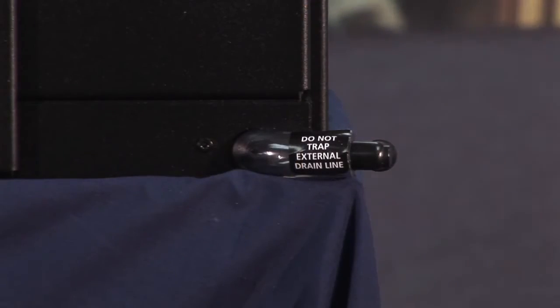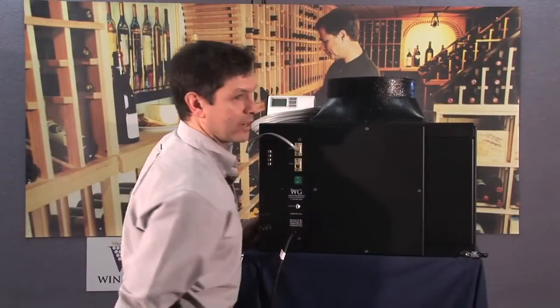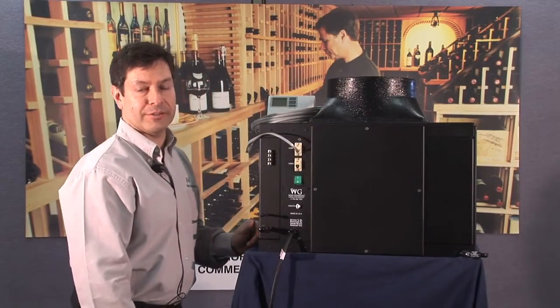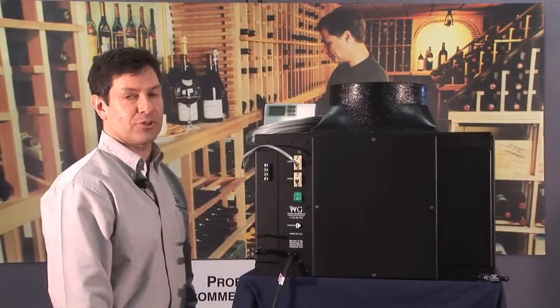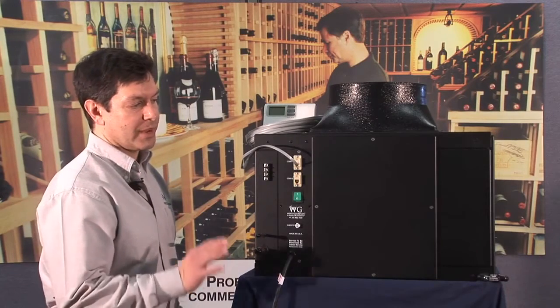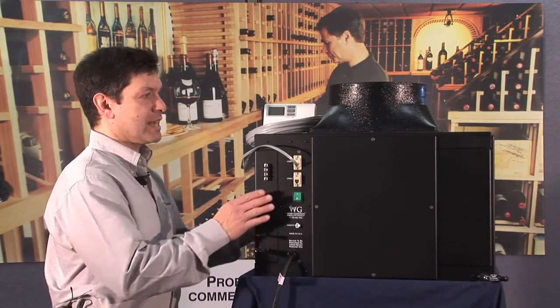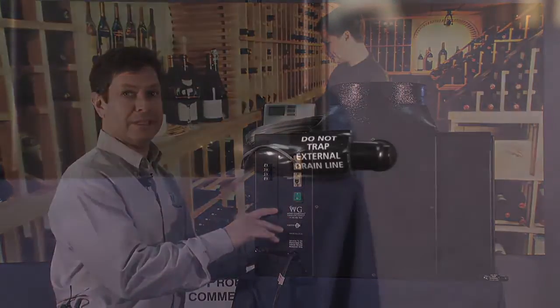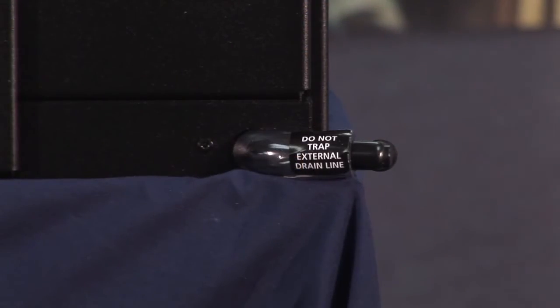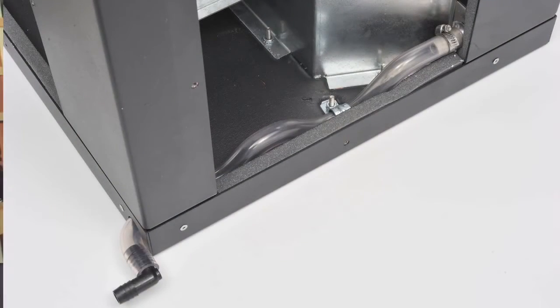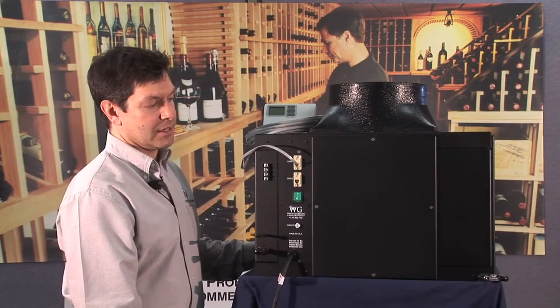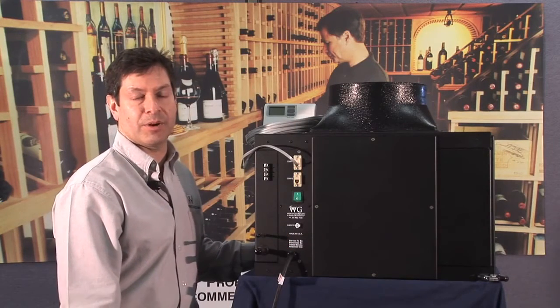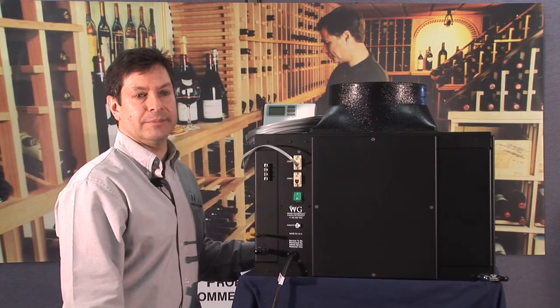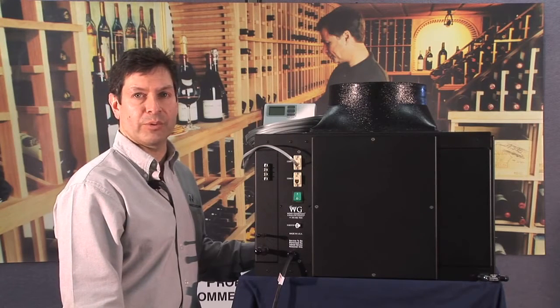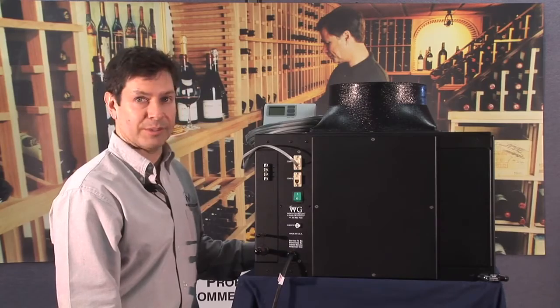And then your drain port connection on the other side of the unit, which will take away any condensate that's generated from the cooling process. It's internally trapped, so when making connections on site, the unit does not have to be elevated too much off the floor, and the drain should not be externally trapped. As mentioned with our other systems, it can cause issues as far as water leakage. That drain can be taken to a condensate pump, open floor drain, open sink, any place where we can just take water away from the unit.